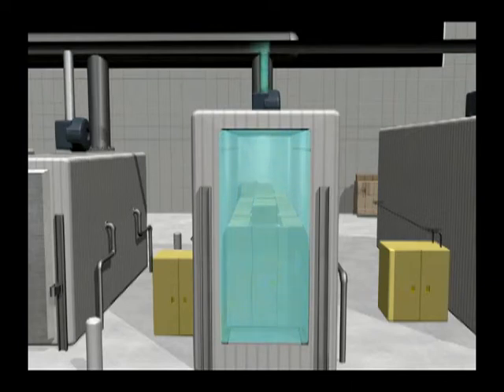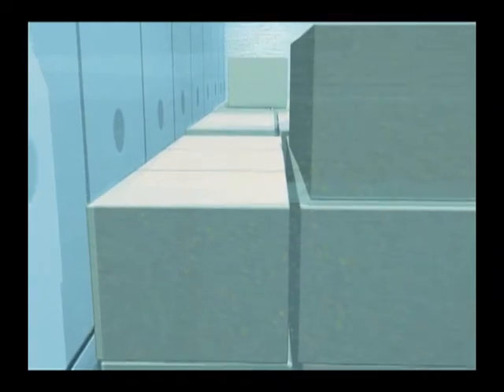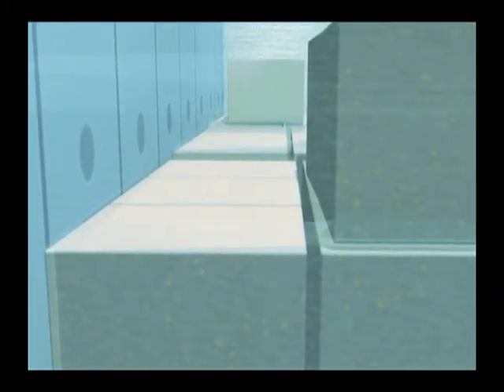This process is critical to reducing the concentration of ethylene oxide to below explosive levels, and is repeated several times until there is only a trace amount of ethylene oxide remaining. This trace amount of gas is not explosive, but it is toxic, and must be removed by ventilating the chamber before workers can enter.